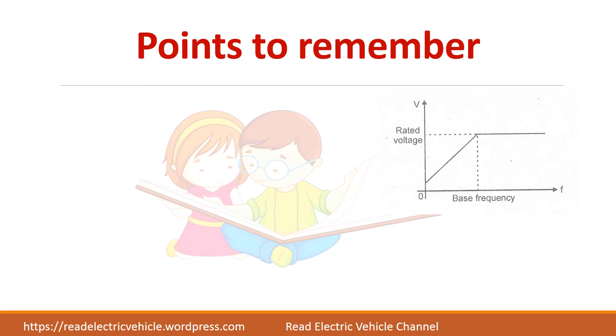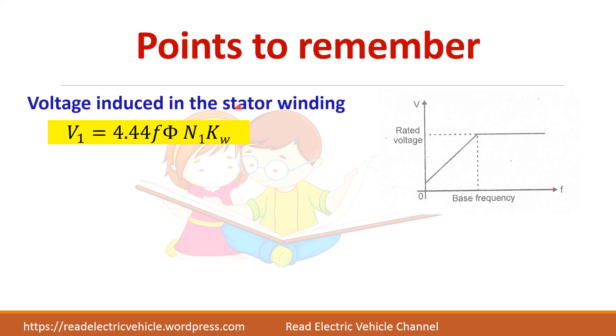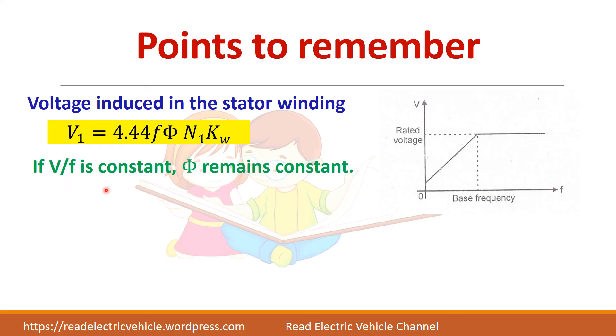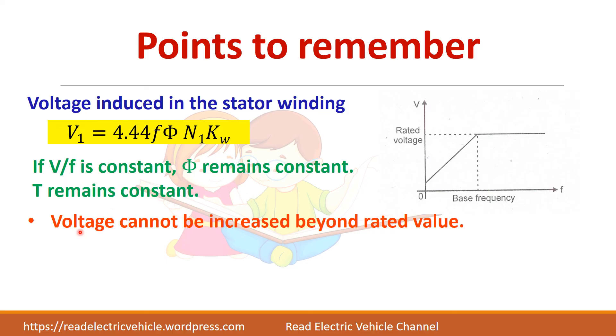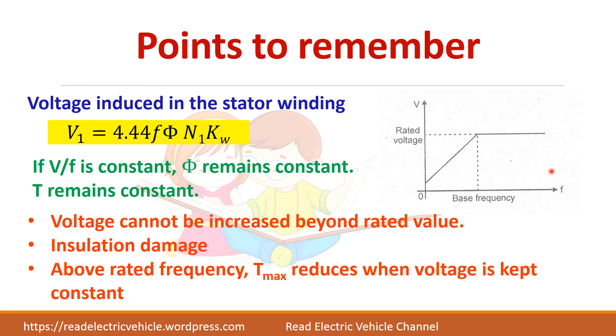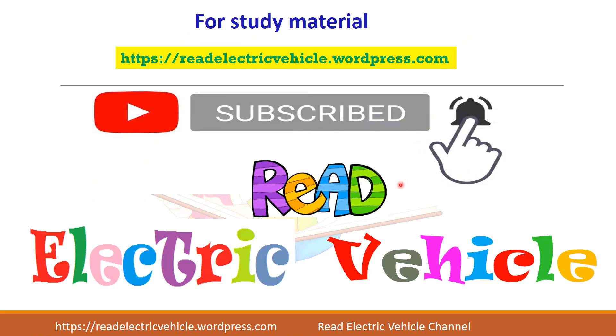Key points to remember: the voltage induced in the stator winding is directly proportional to frequency and flux. If the V by F ratio remains constant, flux remains constant and torque remains constant. Up to base frequency, the V by F ratio is kept constant. After base frequency, voltage must be kept constant to avoid insulation damage, so maximum torque decreases after base frequency.